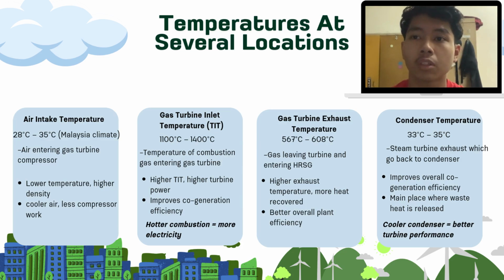So now I'm going to tell you about temperatures at several locations of the Pengerang cogeneration plant. There are 4 locations: intake temperature, gas turbine inlet temperature, gas turbine exhaust temperature, and condenser temperature. For intake temperature, the temperature is 28 to 35 degrees Celsius, which follows Malaysia's climate. Air intake temperature is the temperature of the air entering the gas turbine compressor. Lower temperature means higher density, and cooler air means less compressor work.